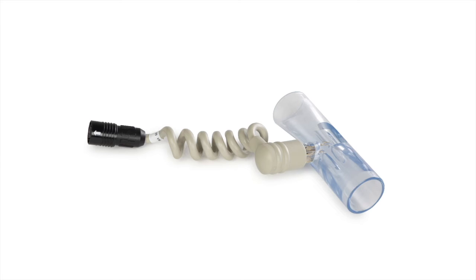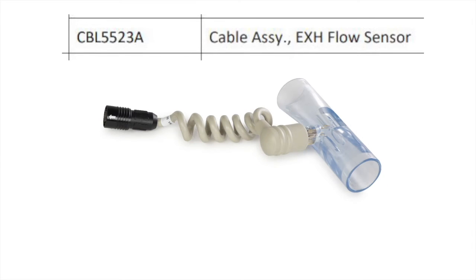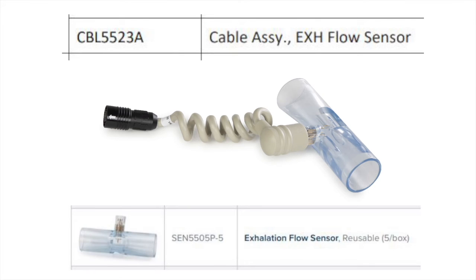This is my exhalation flow sensor cable, as you see it attached to the flow sensor itself. And you simply do not want to try to pull this directly out. Or another thing is turn it counterclockwise or clockwise or twist it out. I've had calls where these have been broken off in the machine.